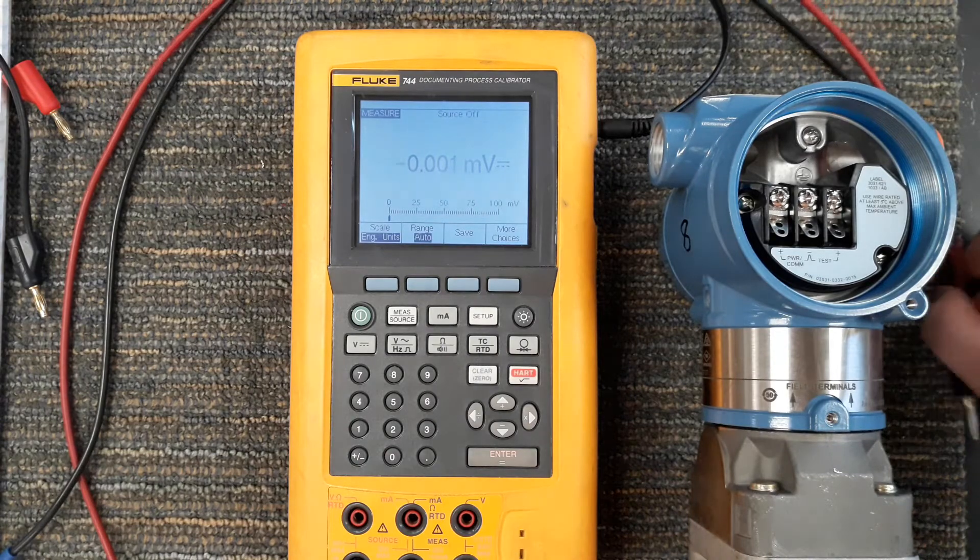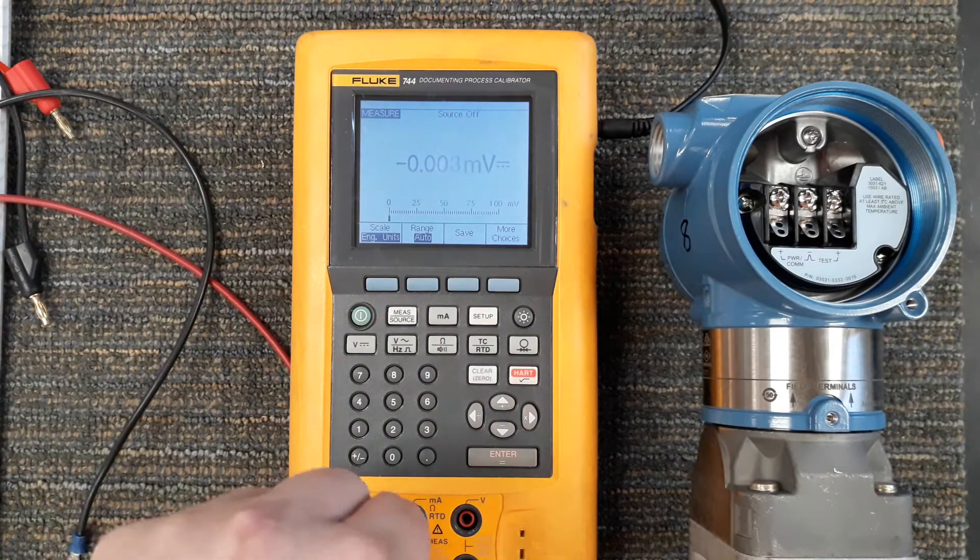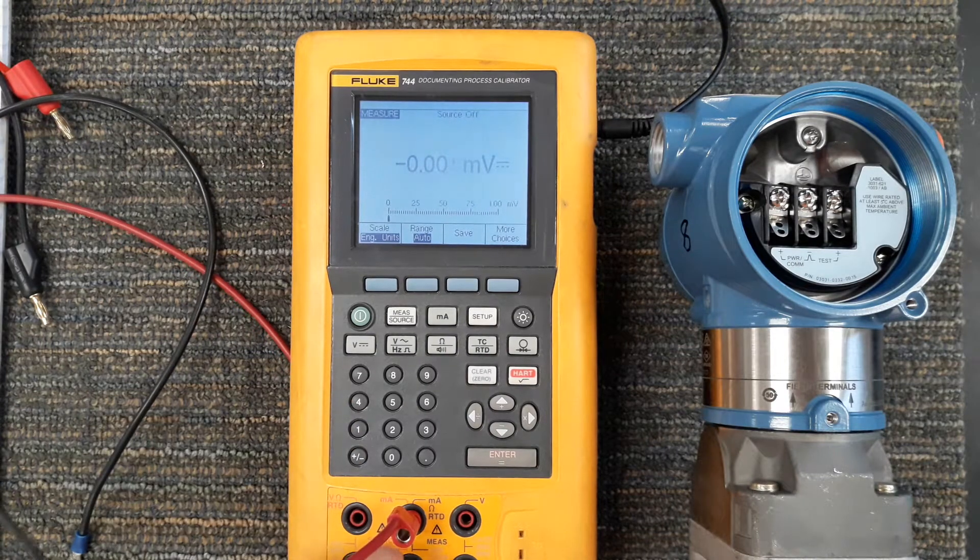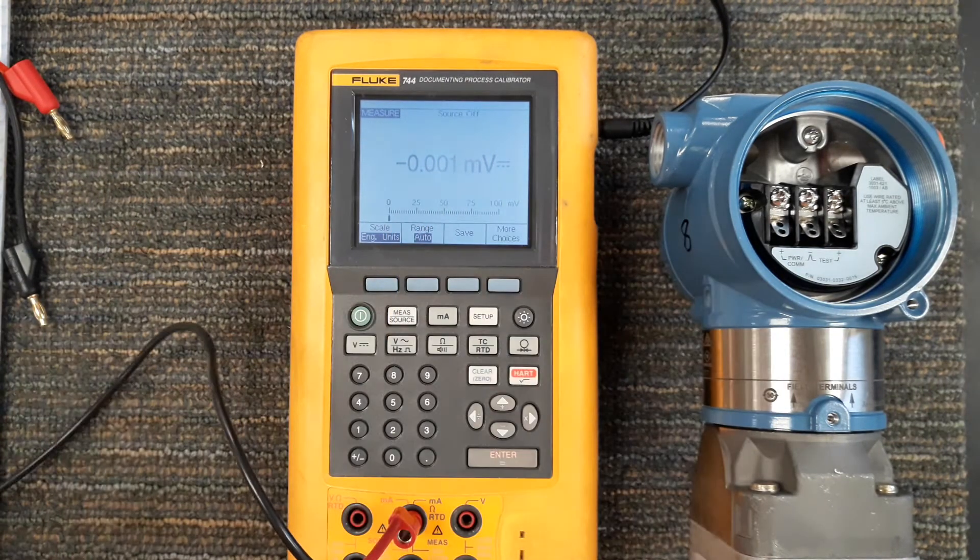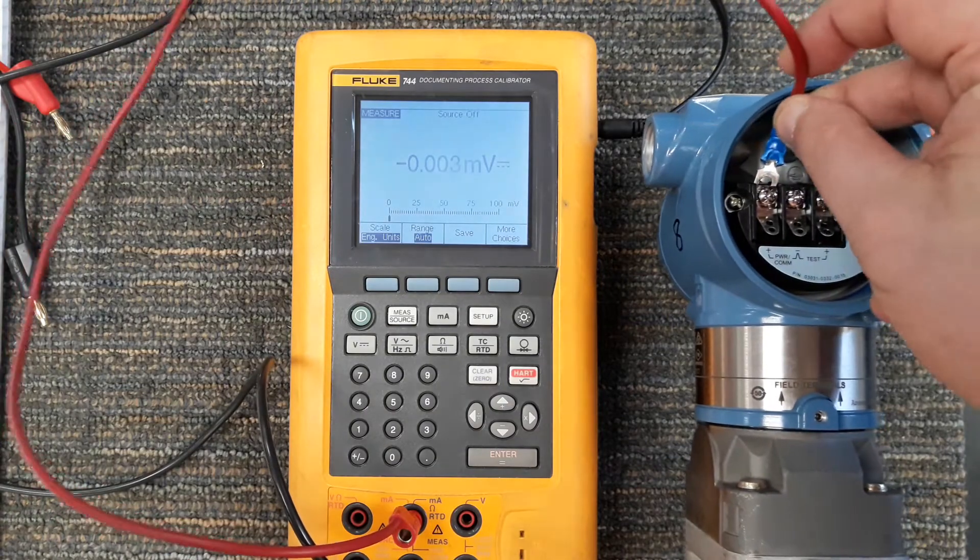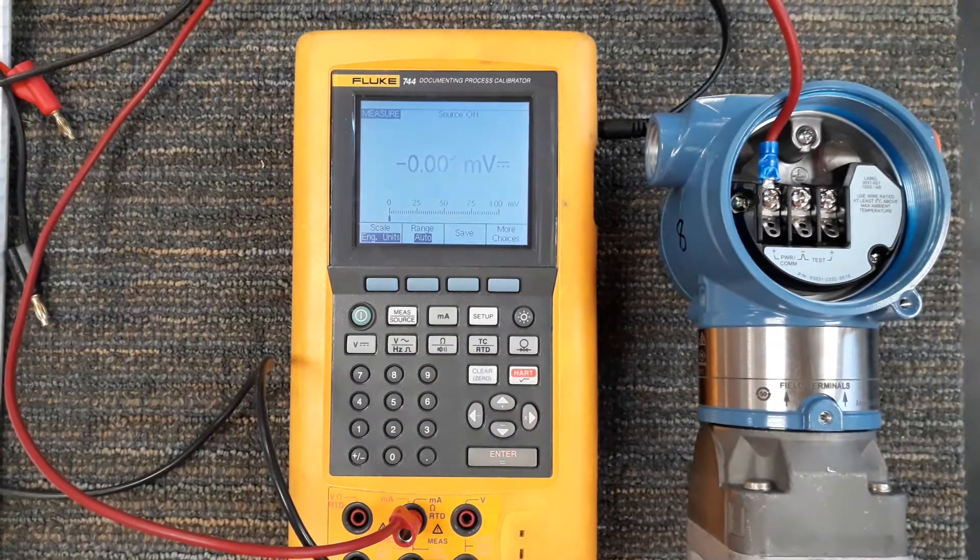Just like we showed in a few videos ago, I want to provide the loop power so I'm going to hook up to the milliamp ports. I know loop power is not being provided because it's not at the top of the screen. I'll go ahead and terminate my wires, red to positive, black to negative.